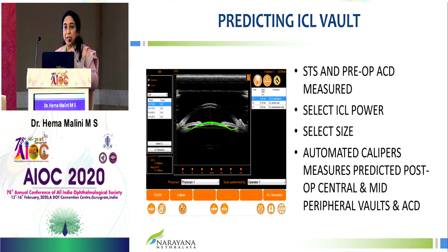This also has a unique software that helps us in predicting the ICL vault. So if we have calculated a particular ICL size preoperatively using the white to white, we can always use the predictor software on the Compact Touch UBM to get the approximate vault postoperatively.